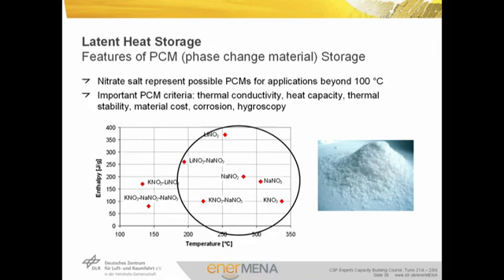Constant temperature energy storage can be implemented using latent heat storage material. Here, the energy associated with the phase change of the storage material is used for energy storage. Candidate materials for the temperature range exceeding 100 degrees are nitrate salts. Important criteria for the selection of phase change materials include thermal conductivity, heat capacity, thermal stability, material costs, corrosion, and hygroscopy.